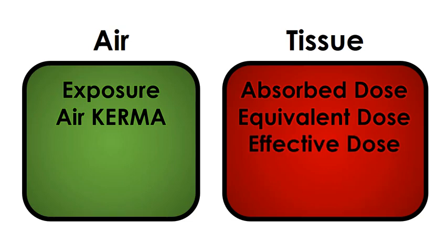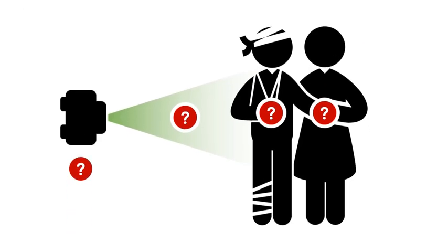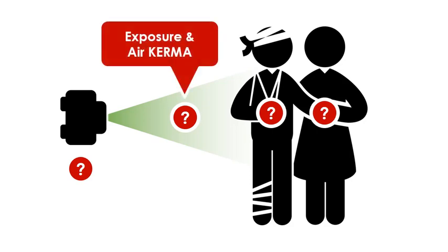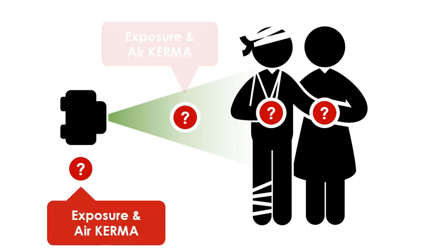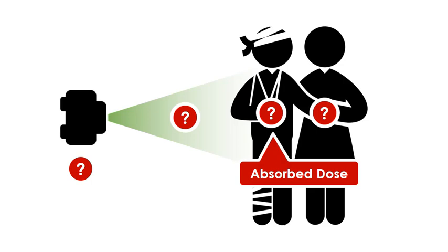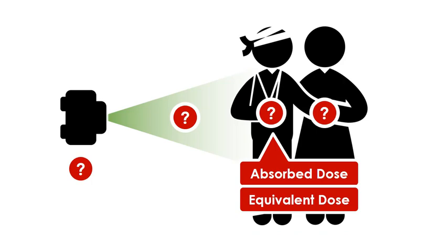All of these measurements are different but related. If we wanted to, we could measure each of these values during a single x-ray exposure. The intensity of the x-ray beam is usually measured as the exposure or the air kerma, which tells us how much radiation is coming out of the x-ray tube and is directed at the patient. We could also use the air kerma and exposure to measure the leakage radiation escaping the tube housing. The dose to the patient or the radiographer is first measured as the absorbed dose, which can then be calculated and converted into the equivalent dose, and the equivalent dose can be converted into the effective dose.